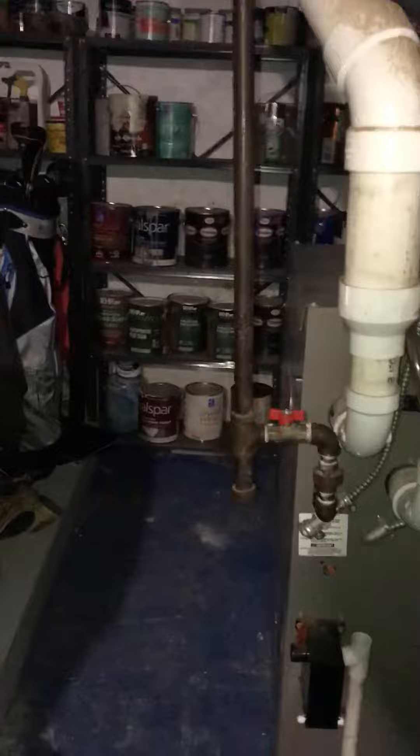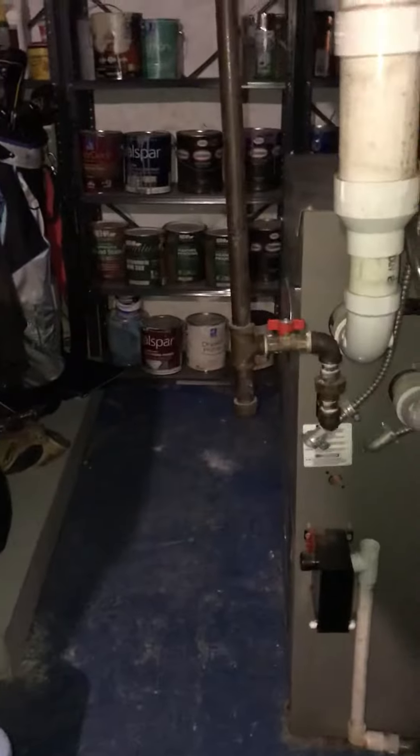We do have an isolating valve and drip on the gas. You can see the electrics are all in a sleeve. The drain is running vinyl and it looks like it's running across the floor to a drain at the back. The line set, as I showed outside, is really close by so we'll replace that — it's just kind of going between the return drop and out.